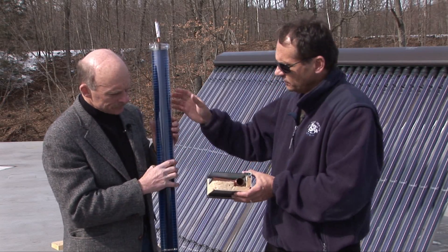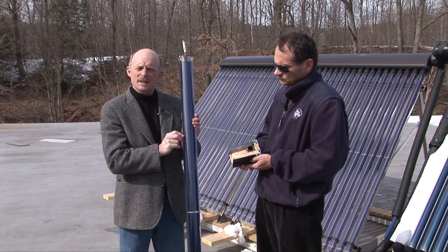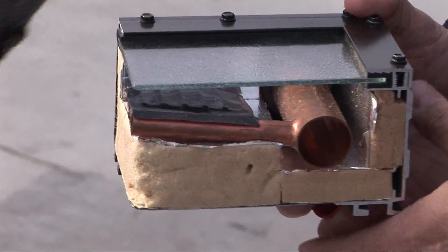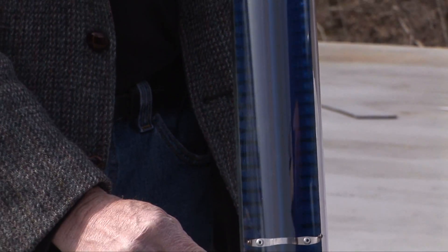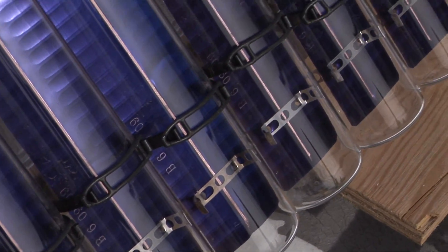And the evacuated tube — having a vacuum inside, I trust there is some value to the vacuum. Could you touch on that? The evacuated tube is a different way of capturing the BTUs that come from the sky. In the flat plate, we have physical insulation; here we have a vacuum. Like a thermos bottle, the heat inside is not allowed to escape outdoors because convection and conduction are eliminated by that vacuum layer. By having this tube, we have a strong surface that can withstand a 35-millimeter hailstone. The structural strength of the borosilicate glass means these are not fractured.